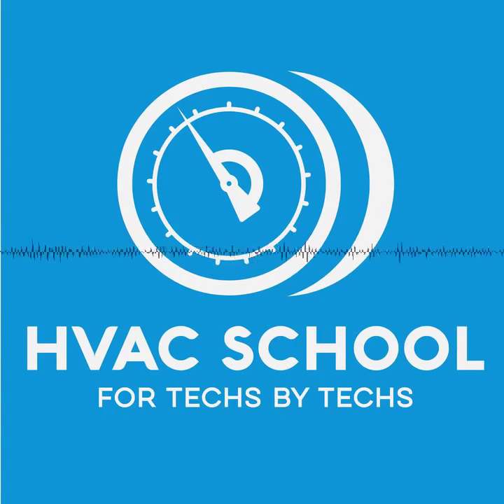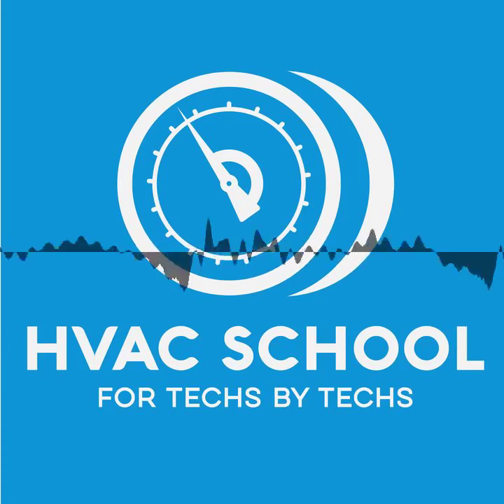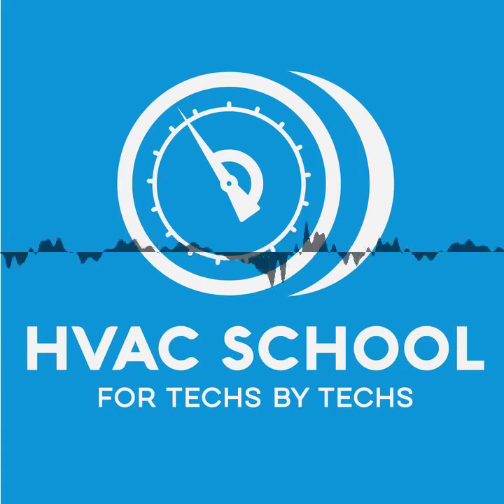The one thing that's worth saying here when we're talking about assembly lubricants, even Nylog, which again, I'm a refrigeration technologies loyalist and I love Nylog, is that if you use too much of it and you get too much of it on the threads especially, it can change your torque spec. So if you're using a torque wrench, you have to recognize that using some lubricant is going to change your torque spec, and you're definitely going to want to stay on the low side of your torque rating when you are torquing down that fitting, because the torque ratings are designed without lubrication on the threads themselves because they don't know what type of lubricant you're going to use, and obviously that changes the torque spec.